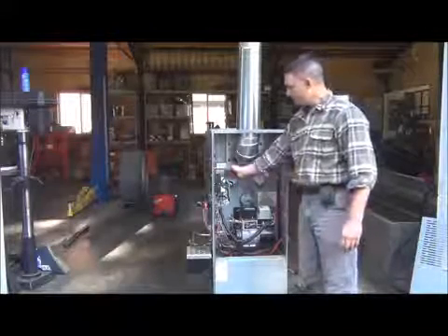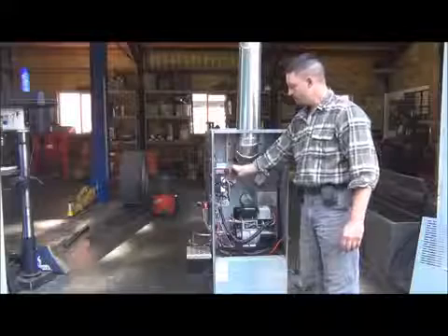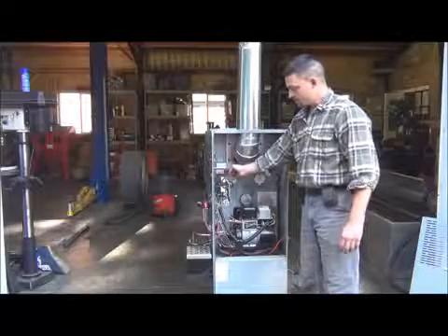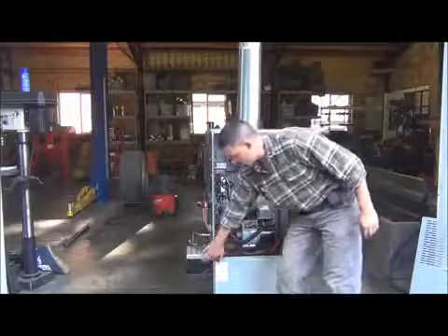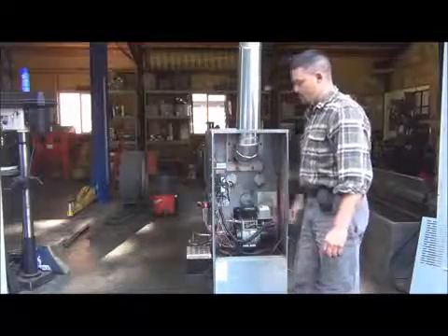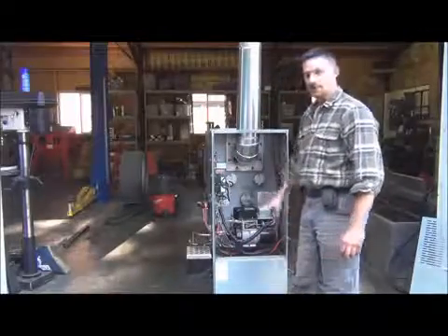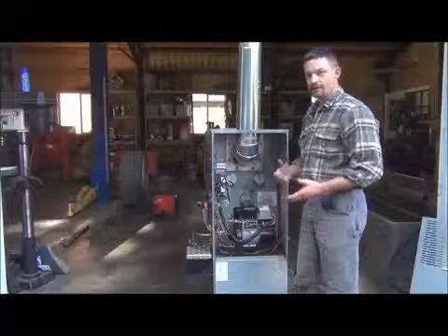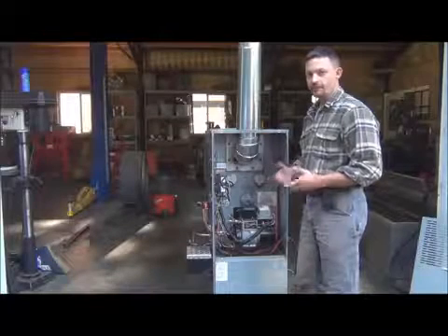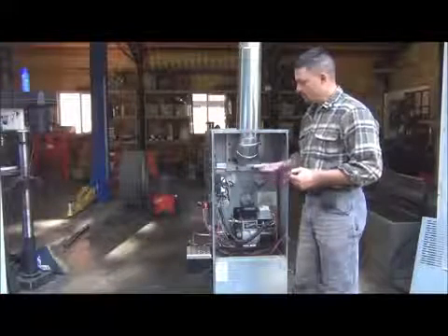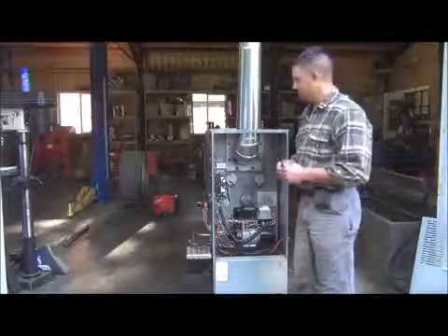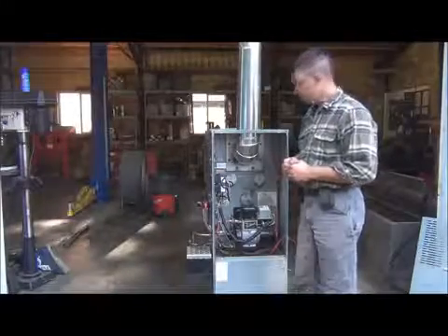It's just a regular digital wall thermostat like you'd see in a house. And whenever the thermostat requests heat, that turns this relay on, which energizes all the components inside the cabinet. And then I have my heater safety relay. What this relay does is, if the level in this oil tank down here is too low, it prevents the heater from turning on inside of there. If you actually uncover the heater element, it can burn up if it's not completely submersed in oil. So if the oil level's too low, this relay just doesn't allow the heater to turn on.